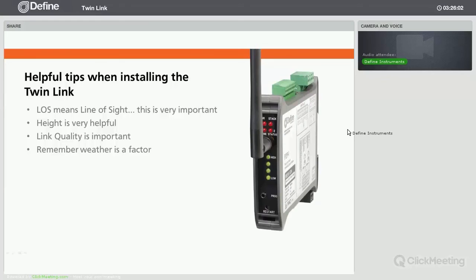For example, if you mount the TwinLink at floor level, the signal has more objects to go through, and this compromises the signal strength. By simply mounting the TwinLink at ceiling height, the wireless signal does not have to go through any furniture or machinery to get to its destination, improving your signal strength. Link quality is also very important. While the TwinLink can transmit when the link quality is low, a high signal strength will be much more stable. And for outside installations, remember weather can be a factor. If you have a low signal strength on a fine day, it won't improve in a rainstorm.